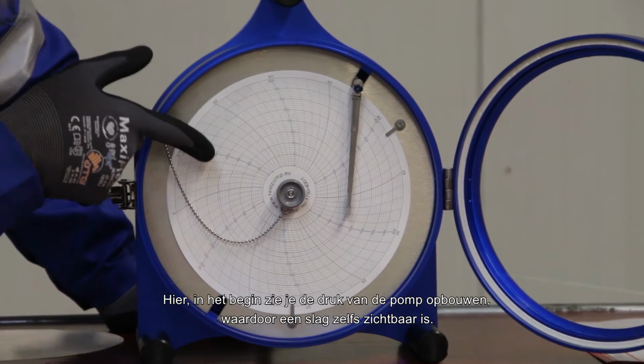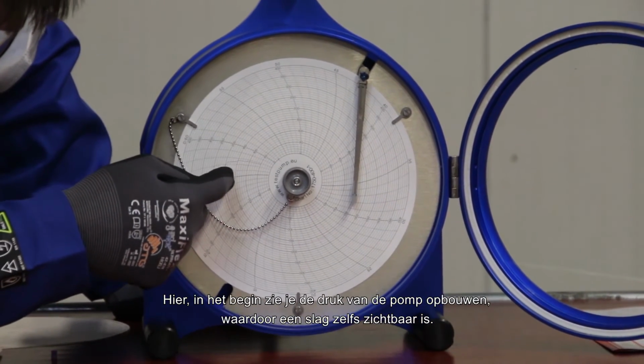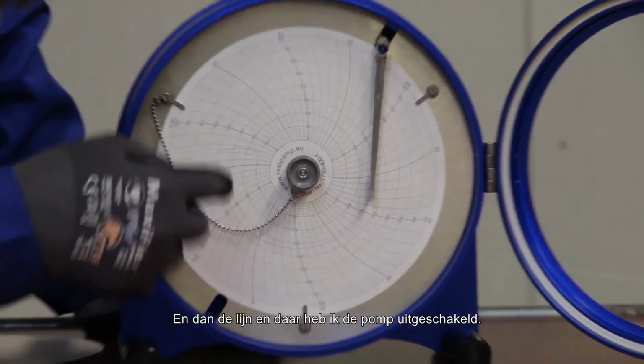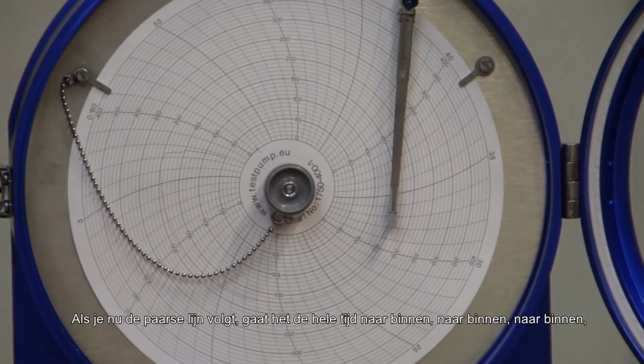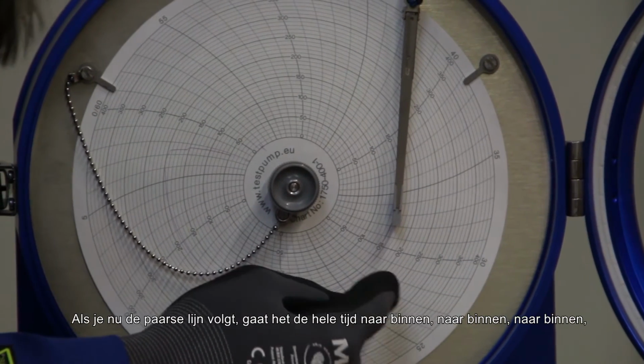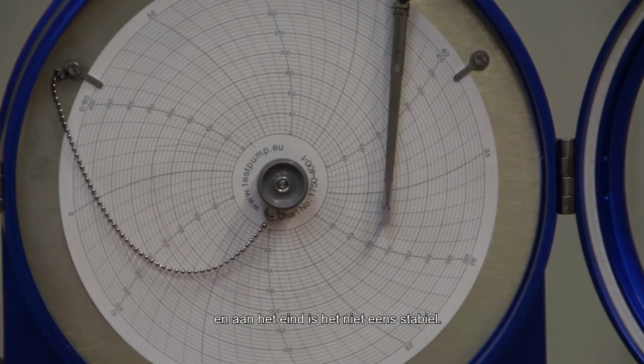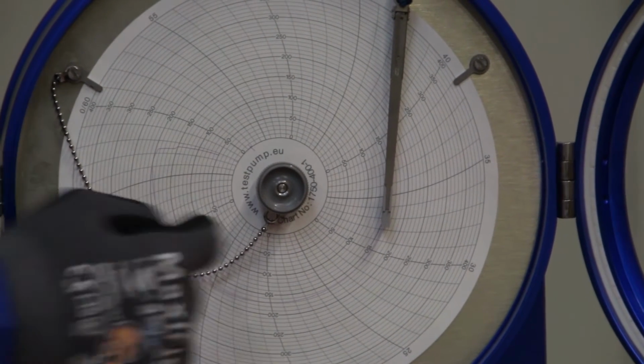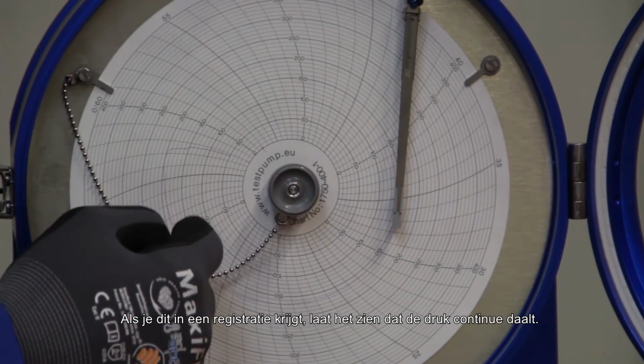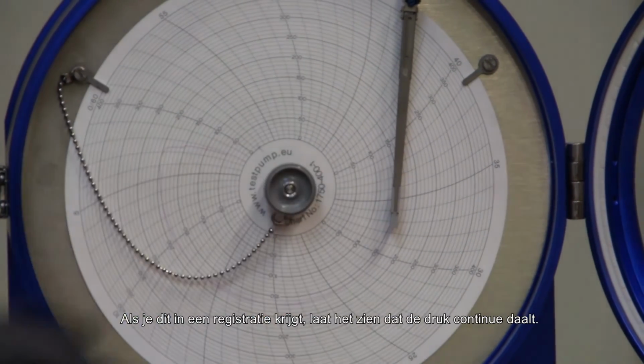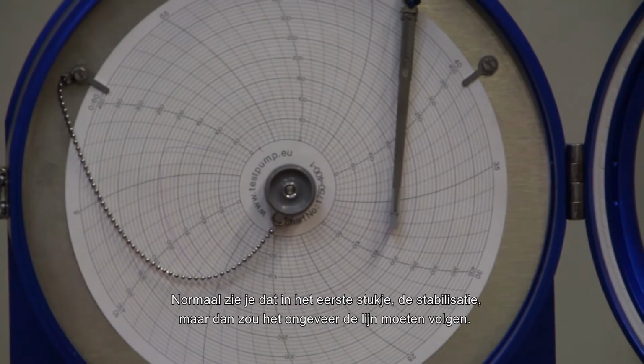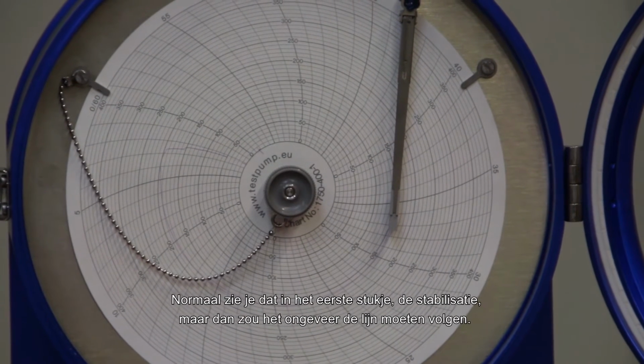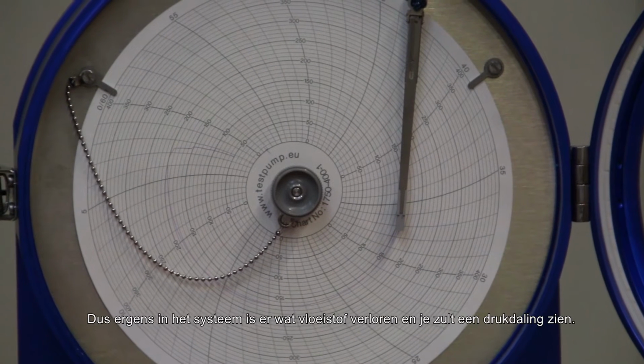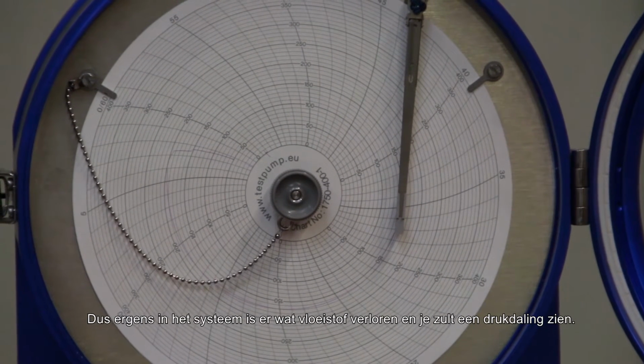Here, in the beginning, you see the pressure build up, the pump making a stroke is even visible, and then the line, and that's where I cut the pump. If you now follow the purple line, it's sort of going inwards, inwards, inwards all the time. And it is not even stable at the end. Of course, if you get this in a recording, it will show that your pressure is dropping all the time. Normally you will see that in the first bit, the stabilizing, but then it should sort of follow the line. So somewhere in the system there is some fluid lost and you will see a pressure drop.